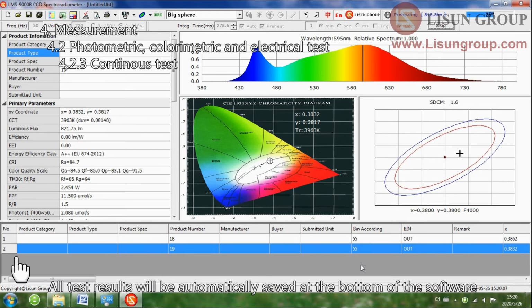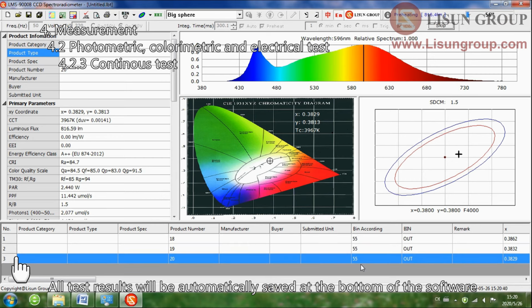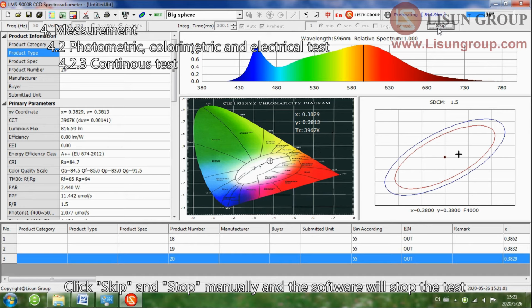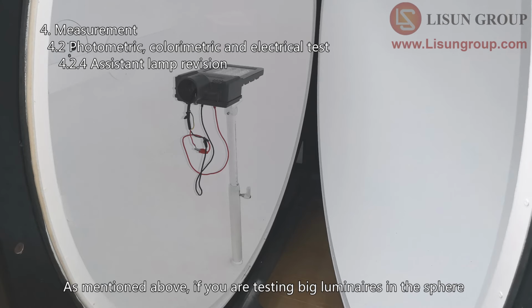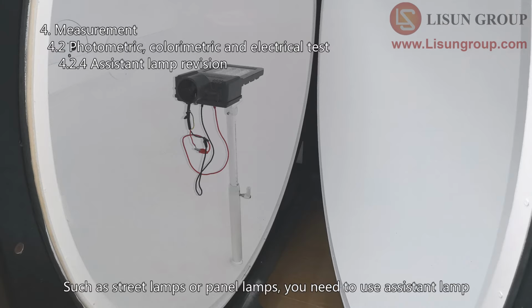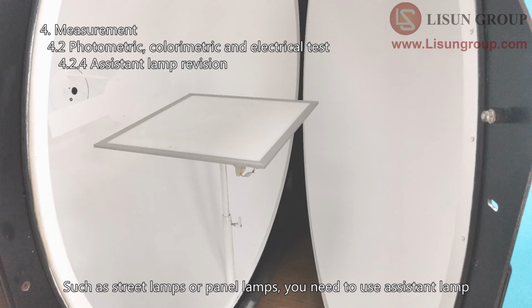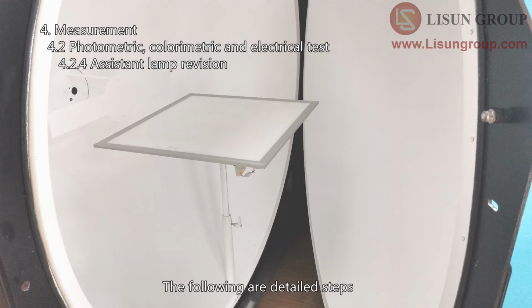All test results will be automatically saved at the bottom of the software. Click skip and stop manually, and the software will stop the test. As mentioned above, if you are testing big luminaires in the sphere, such as street lamps or panel lamps, you need to use an assistant lamp. The following are detailed steps.